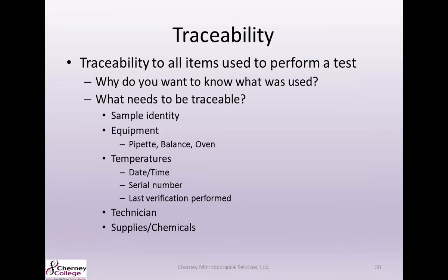Continuing with traceability, why do you want to know what was used on your samples? Well, if there was an issue with a balance that was used to weigh out a sample and it was later discovered that the scale was out of spec, you would want to know and be able to trace back which test results would have been affected.